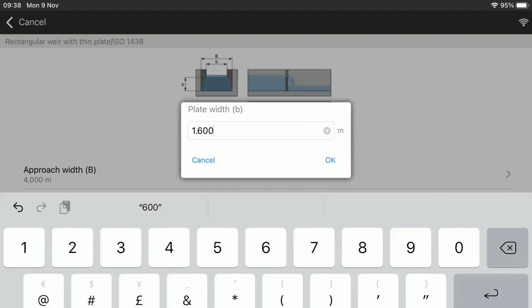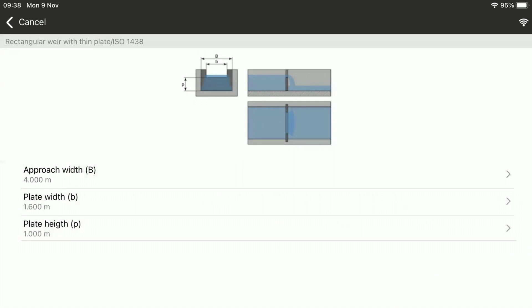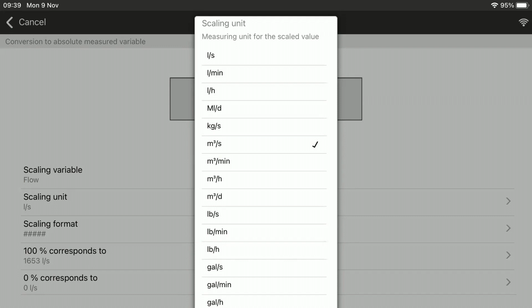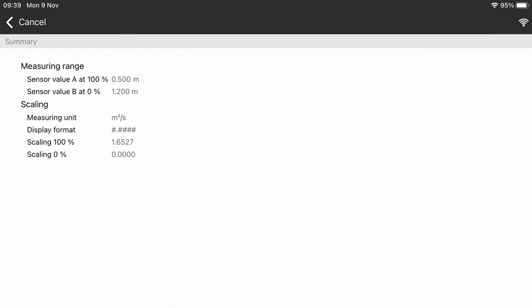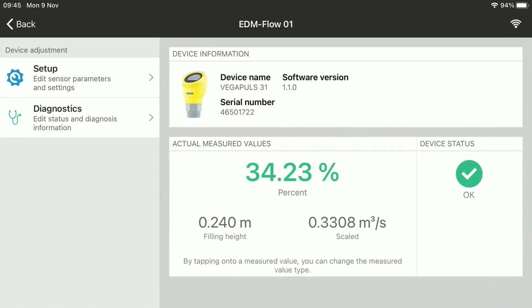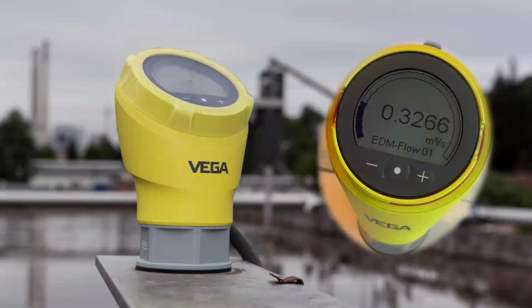And then we can continue to set up the dimensions for this particular primary flow device. So you can see we have the approach width, the plate width, and the plate height. Next, we can select the engineering units we want, the flow units. So in this case, we've selected cubic meters per second. And then we continue through the wizard and it gives us a summary, and that essentially is the setup completed. When we come out of the setup, we can see on the display here that we have filling height and we have scaled flow rate displayed with the VEGA Tools app. So a nice flexibility and good visualization. If we look at a radar sensor with a local display, it also has bar graph indication. You can see the tag number, the EDM flow 01 tag number, and we can see our engineering units in cubic meters per second.